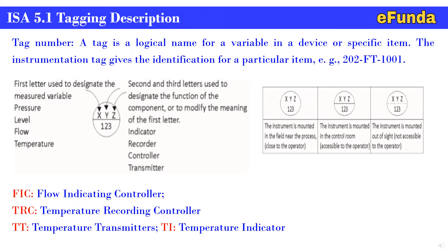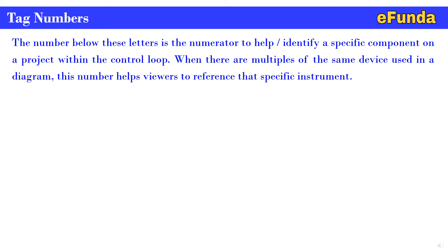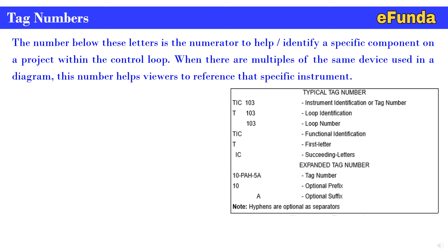This is how the tagging convention is assigned in the instrument industry, and for that ISA 5.1 tagging description is mainly used by all the clients. Tag number - the number below the letters is a numerator to help identify a specific component on a project within a control loop. When there are multiple of the same device used in a diagram, this number helps the viewer to reference that specific instrument. One can see the typical tag number indicated on the right hand side where TIC-103 is the instrument identification or tag number. T-103 is the loop identification, 103 is the loop number. This is how the nomenclature is being used for the tag number.